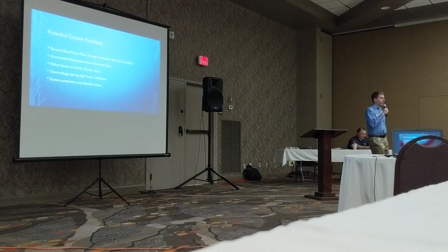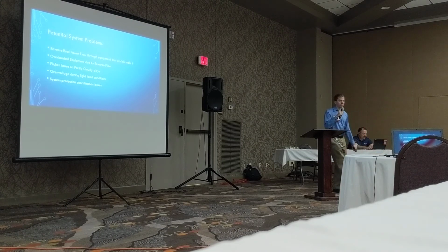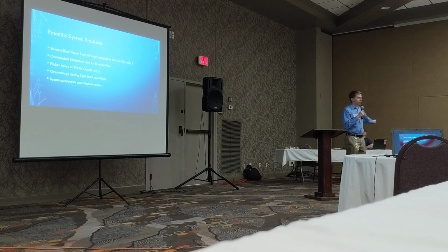So we talked a bit about some potential system problems: reverse real power flow through equipment that can't handle it. A lot of devices have been set up for 100 years to look in one direction — specifically voltage regulators and some protective devices, where the source is on one side, the load is on the other, and it behaves that way and everything works. But if you're feeding backwards, all of a sudden you're regulating in the wrong direction, and your controller doesn't know what to do.